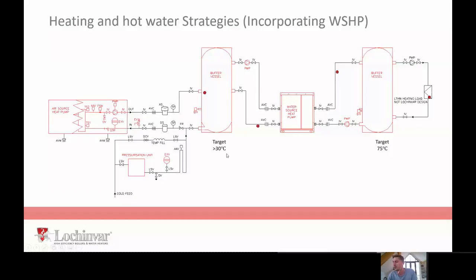So what we find is on a lot of retrofit applications, a lot of buildings like that, this sort of setup is quite favoured because what you end up with is a system that you can plug onto existing infrastructure, and you can work at these inflated flow temperatures, but still incredibly efficiently. It's not as high as you'd hope, you know. I mean, like a dedicated hot water system from a heat pump, I'd be looking at a SCOP of 3 to 3.2, so up to sort of 320%. A heating system at 50 degrees, you'd be looking at an efficiency of probably 350, 360%, which is massive.